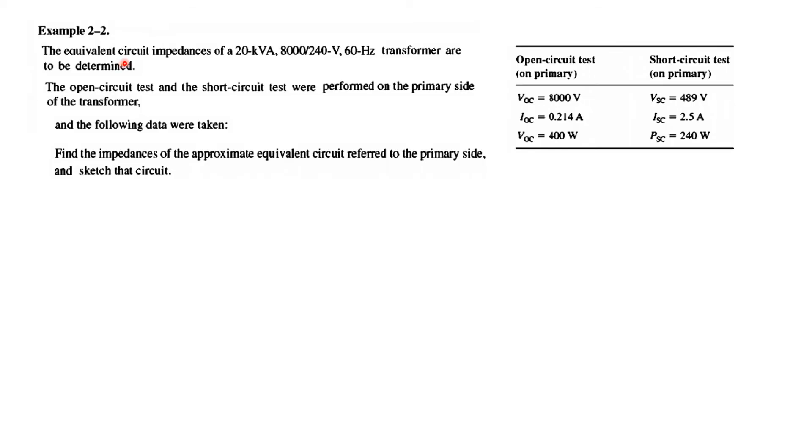Here is an example. The equivalent circuit impedance of a 20 kVA, 8000 by 240 volt, 60 hertz transformer are to be determined. The open circuit test and the short circuit test were performed on the primary side of the transformer. And the following data were taken. So these were the results for the open circuit and short circuit test. Find the impedance of the approximate equivalent circuit. Keep in mind, we have to use the approximate model. Refer to the primary side and sketch the circuit or find the value of the components actually. So this model we'll be using, this is referred to the primary side. And this is the simplified or approximation equivalent model.